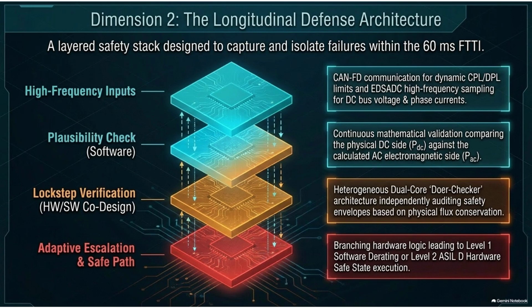So it multiplies the DC voltage and DC current, and then cross-references that against the AC electromagnetic power being generated at the motor. Okay, so by multiplying the three-phase AC voltages and currents and factoring in power factor and mechanical losses. Exactly.